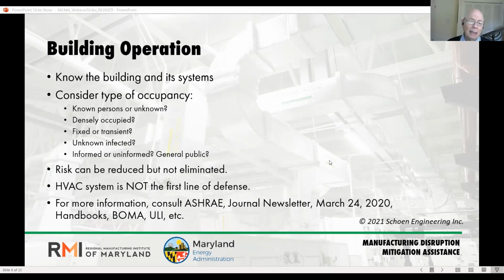Here's what I meant by the HVAC system playing a small role. It's really not the first line of defense. In indoor air exposure, we always say the first rule is source containment. Whether it's a smelly process you won't bring into a room, or a process with dedicated exhaust, we try to get contaminants out before they enter the rest of the room. So the HVAC system, other than spot exhaust, is not the first line of defense.